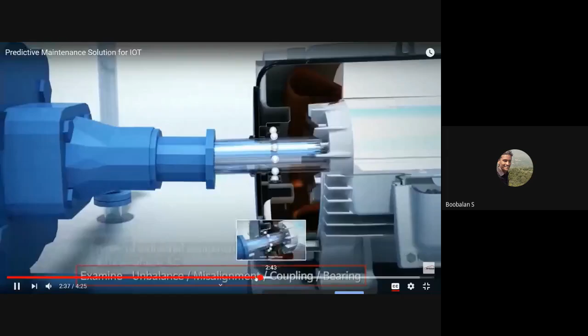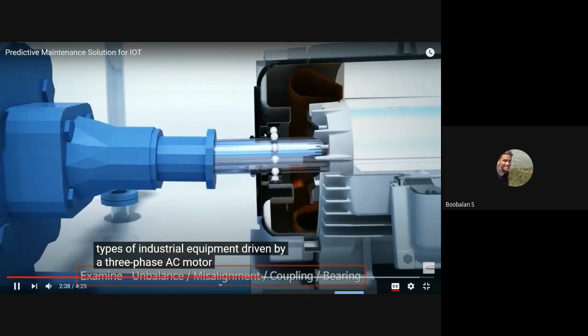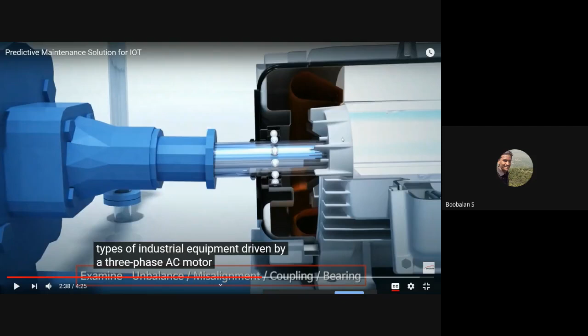Now we will have an accelerometer, right? So once we install an accelerometer in the motor, because why is this misalignment happening, right? There is a load, that's called a blower motor, connected to the motor shaft, right? So there is a bearing malfunction happening. There is a big misalignment with the motor shaft as well as your blower coupling. So this is a small arrangement that measures your vibration as well as a torque sensor, right? Due to this misalignment, your rotor is also getting misaligned. So due to that, we will have a spark also getting introduced.